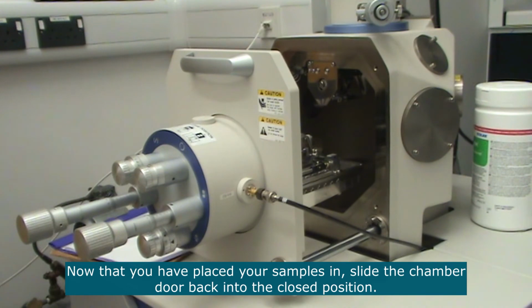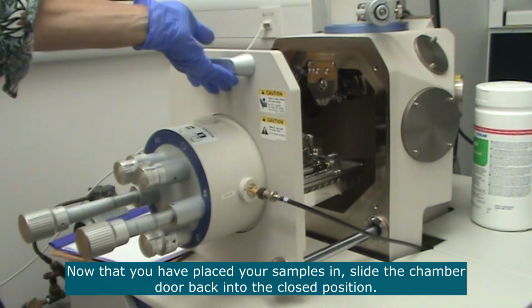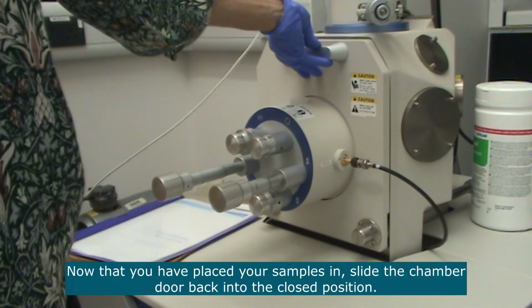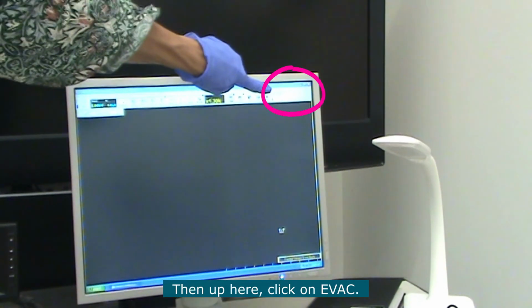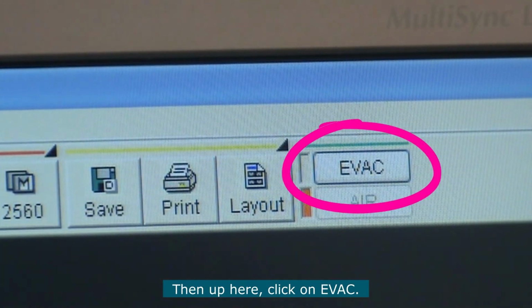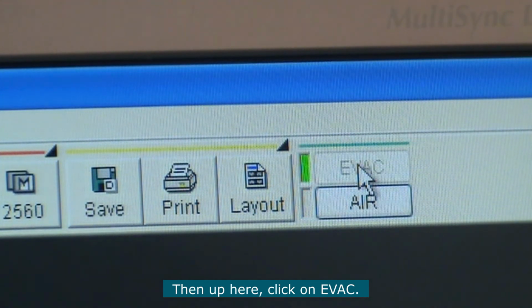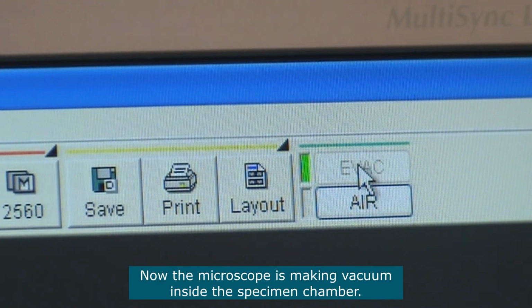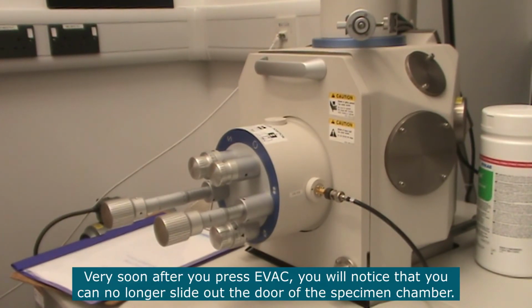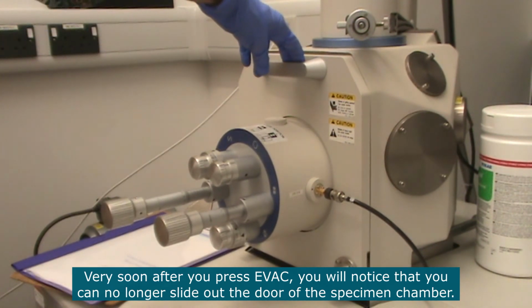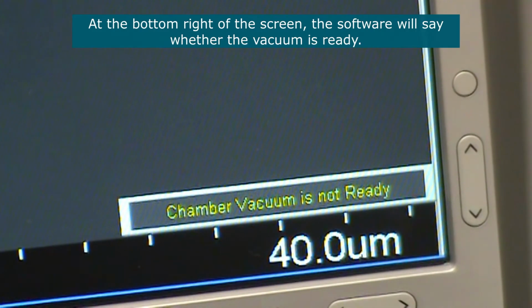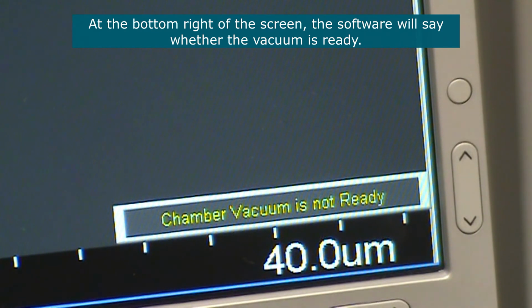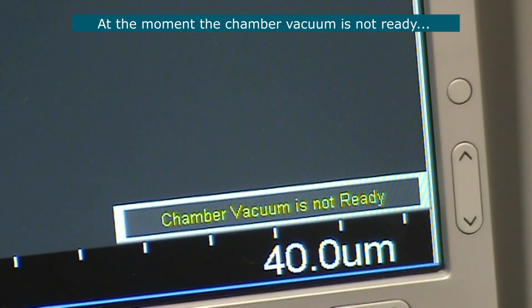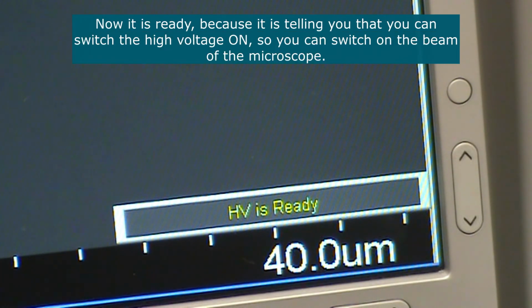Now that you have placed your sample inside the chamber, then slide the chamber door back into position, and then up here click on evac. Now what the microscope's doing is that it's making vacuum inside the specimen chamber. Very quickly after you press evac, you should feel that you can no longer slide out the door of the SEM. At the bottom right of the screen here, the microscope will say whether the vacuum is ready. At the moment, the chamber vacuum is not ready, and now it's ready because it's telling you that you can switch to high voltage, so you can switch on the beam of the microscope.